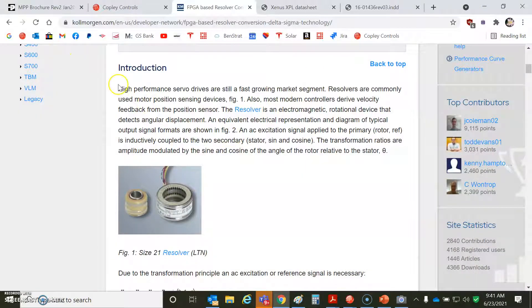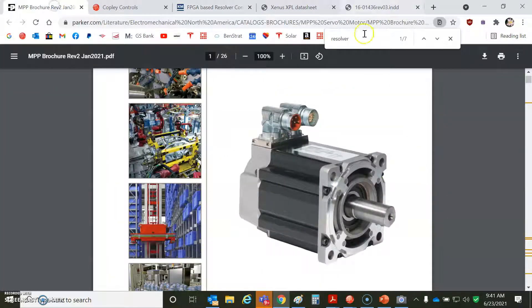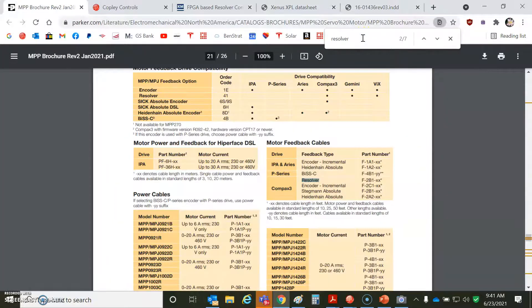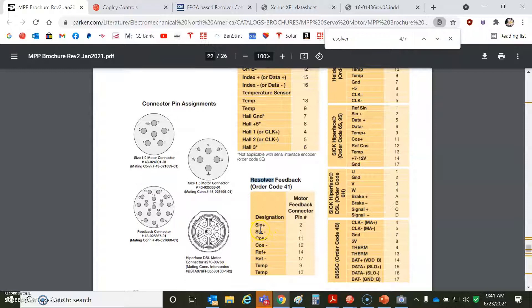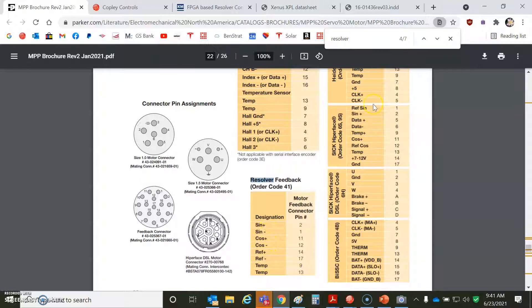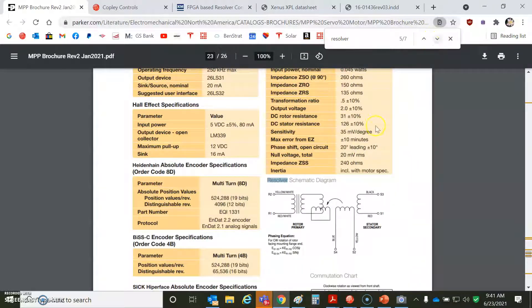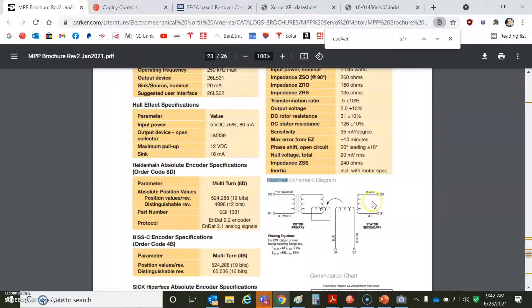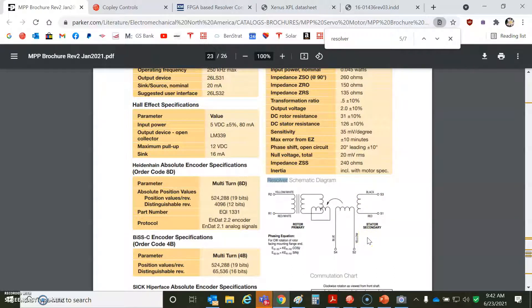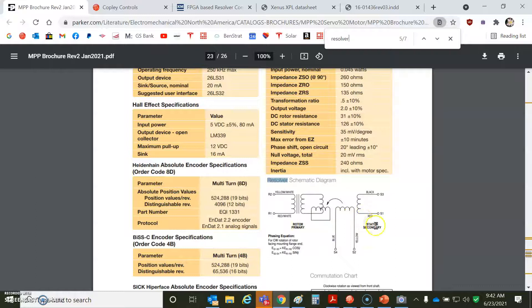We're going to take a quick peek at the motor here. So it's a Resolver motor, and they've got a pinout for sine and cosine. It's a differential pair of sine, cosine, and excitation. We excite it, and there's a temperature. And, of course, the shield gets connected to the drive, not the motor case. But the basic idea is this transformer gets the excitation. And as we rotate through 0 and 90 degrees, the rotor, this is the primary rotary, and then this is the stationary, secondary.